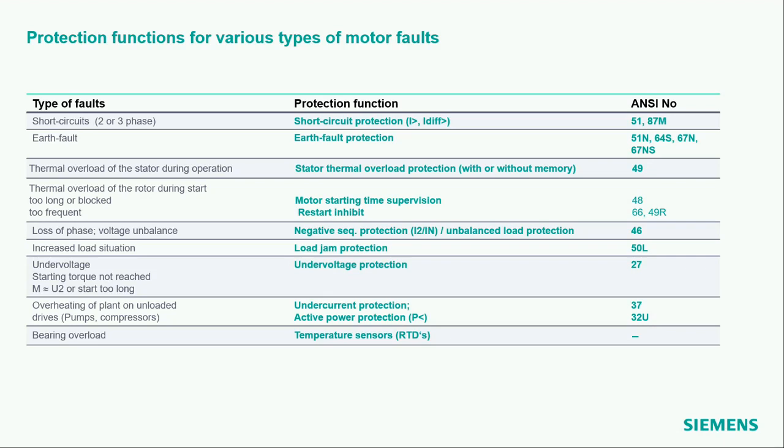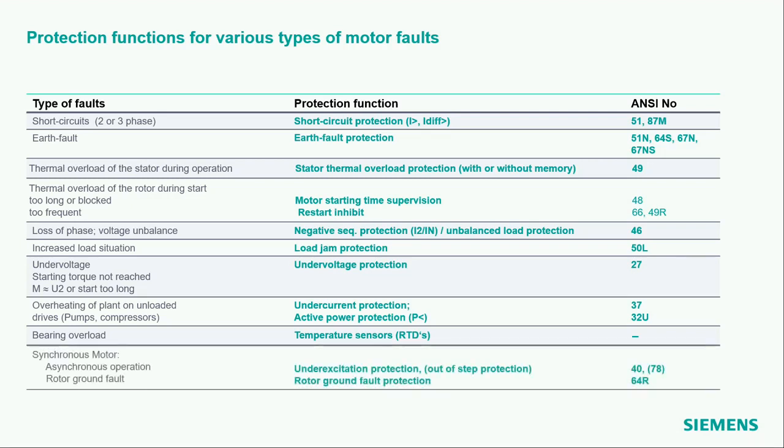Bearing overload, therefore we have temperature sensors, RTD sensors, which are there on the bearing, and we can get this temperature and then give an alarm or even trip the motor if this is too high.